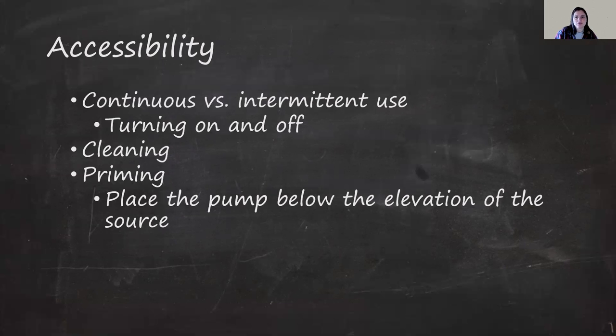Another factor in determining how often you will visit your pump is whether it's self-priming or not. Self-priming means the pump can generate enough initial force to suction liquid from a source generally limited by a given distance. For example, a pump may state it's self-priming up to three feet. This means it can draw water upward into a pump three feet above the water elevation as soon as you turn it on. If a pump is not self-priming, the water source must be above the pump so that gravity forces the fluid into it or there may be a priming chamber. A priming chamber is a reservoir in the pump that you fill with water. When you turn the pump on, the water within the chamber creates enough suction to draw water from the source. Each time you turn the pump on, you will need to ensure the priming chamber is filled.